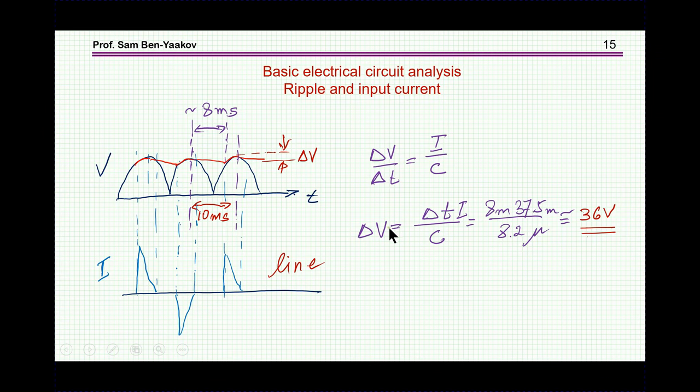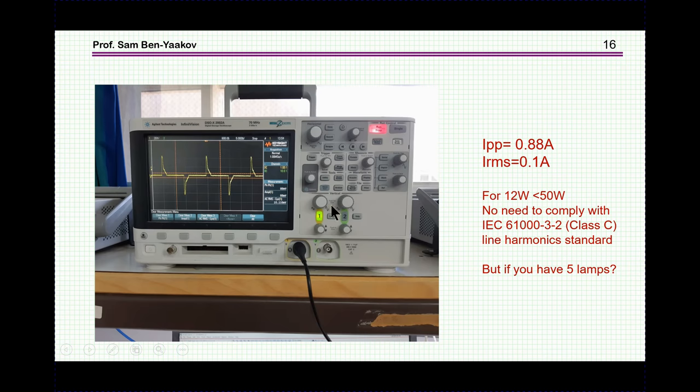Looking now at the real measurement, this is a measurement. We found that indeed the input current is fairly high. It's a peak to peak of 0.88 amps, so it's about 0.44 amp peak each side, fairly high for this 12 watt lamp. But since it's 12 watts, which is less than 50 watts, then it doesn't have to comply with the line harmonic standard. This is IEC 61000-3-2, and we are talking about Class C for lighting, which is starting at 50 watts, so we don't have to worry about that. But if we have say 5 lamps, it's already 60 watts, but the standard doesn't talk about many devices, it talks about one device, so from the point of view of the standard it is okay.